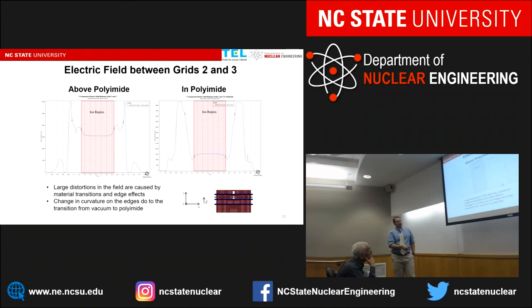So we looked at how the field behaves vertically through the probe, and now how it works horizontally. Again, we're using the same simulations, looking at the vertical electric field, but just across the horizontal portion, like in the bottom right corner there. And we looked at two regions. We looked at above the polyimide insulator, and we also looked at the hole created in the polyimide insulator just above the grids. And as you can see, we have, in general, a pretty flat field, but at the very edges, you get a sharp transition either up or down, which is interesting because that could affect the actual ion energy as they stream down the probe.